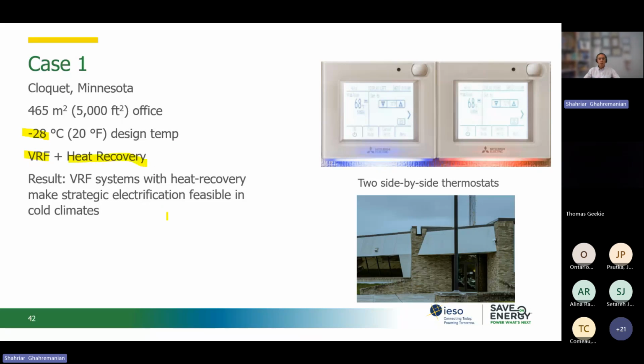And they found in that study that there is no need to even have auxiliary or supplemental heating systems. Basically they retrofitted the building, and in some places, just for the showcase, they installed a light on the thermostat: if the thermostat is providing cooling, it becomes blue. If the thermostat shows red, it means the system is providing heating. They showed that at the same time, anyone can set their thermostat, every zone can have a comfortable area, and they saw savings in their systems. So it's a cold winter zone with hot summers, so it's a good VRF application. They installed it, and they reported in Minnesota that this is a good system.